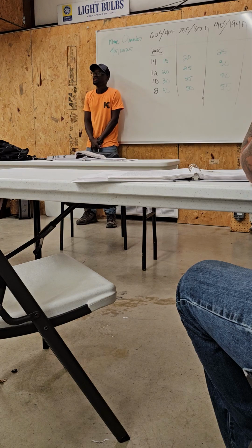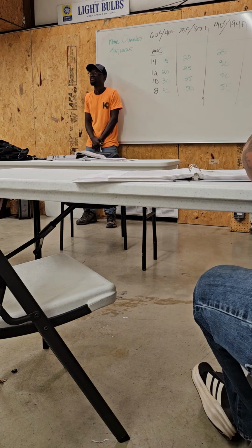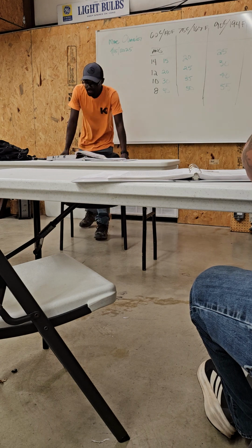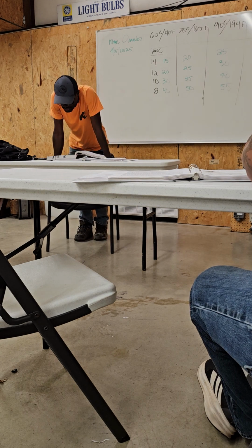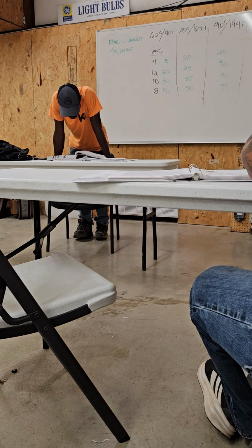Okay, let me ask a question then. Have you ever seen it been done before, where you see somebody pull a bunch of THHN, let's say you're working for Siemens? Have you ever seen somebody put a 30 amp breaker on a number 12? Because that's what the asterisk is for, right? Stating that number 12 is limited to a 20 amp breaker, being a 20 amp circuit.